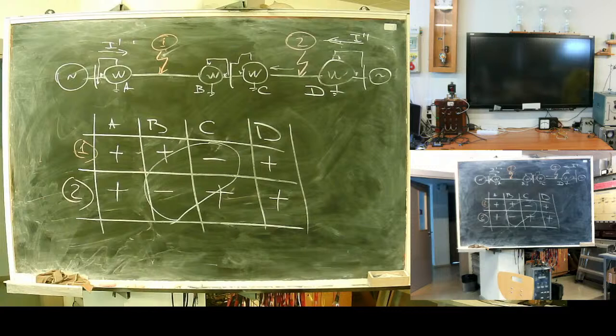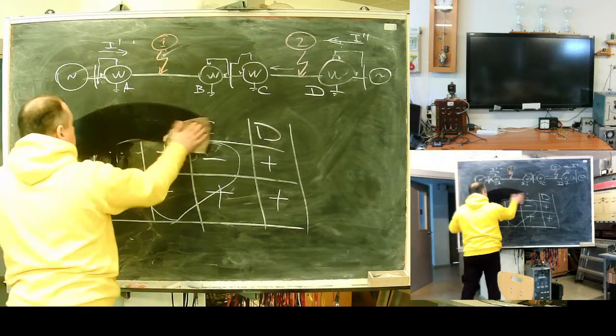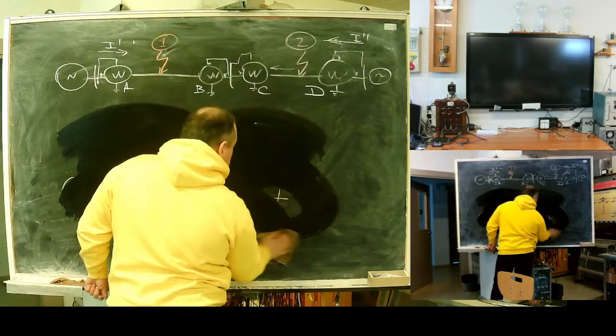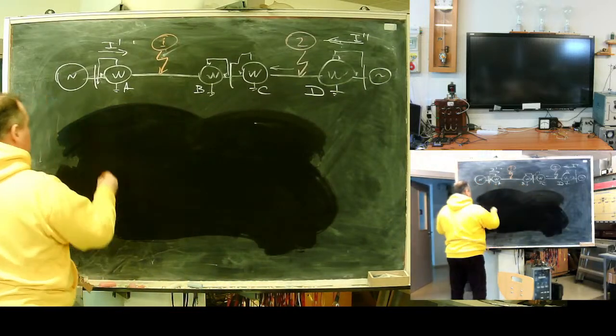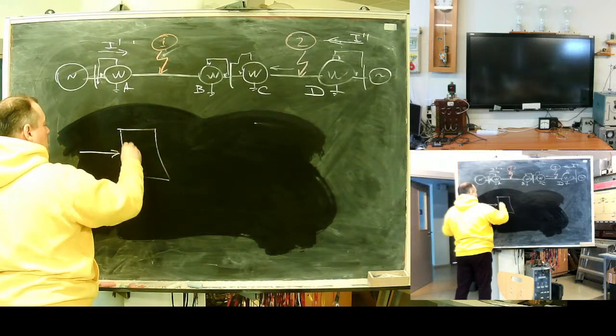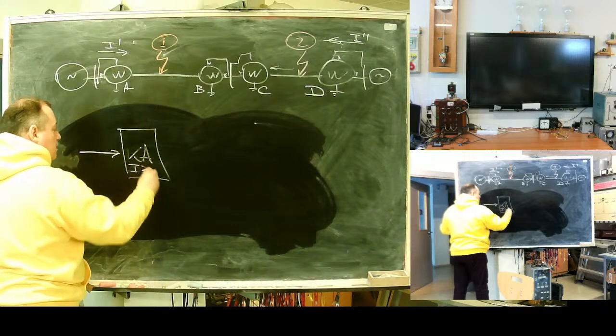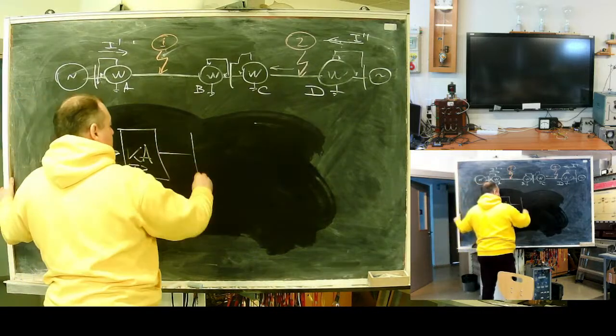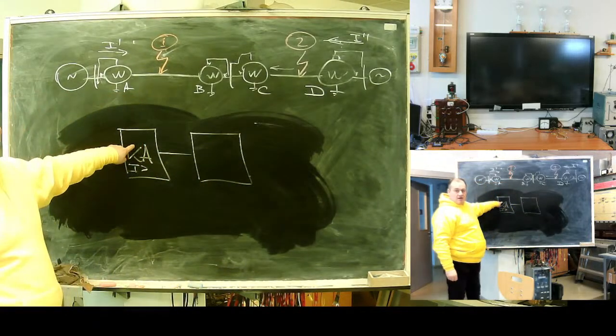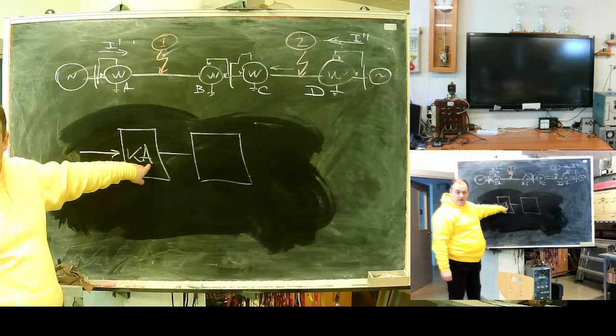What can I see? I see that if I would be able to inhibit protection operation in case of negative power flow, it will solve my problem of double fed lines. Appears I need something like this. KA, overcurrent relay. K means relay, A amperes. So it's an overcurrent relay.